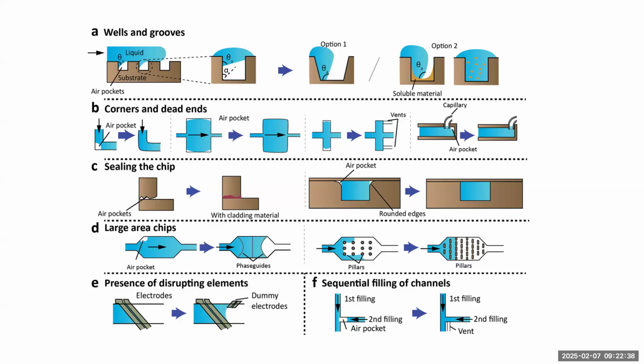The liquid will go right up to the vent, but not go through the vent and exit the device. So you have to make sure that your size is correct and that you have a way to make your venting hydrophobic. And you can do that with different materials. They're not on the tip of my tongue right now, but again, we can follow up in comments if this is something that interests you.